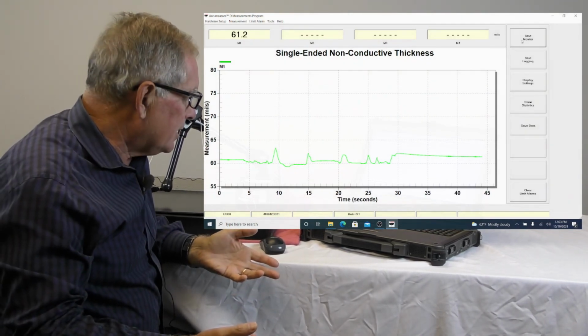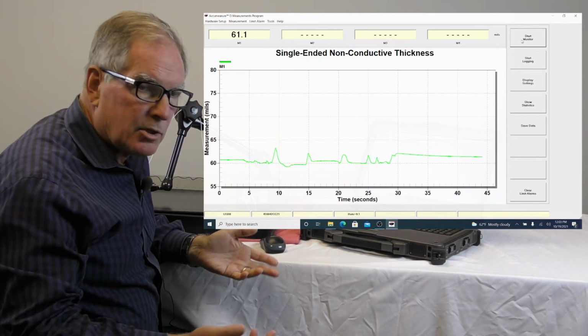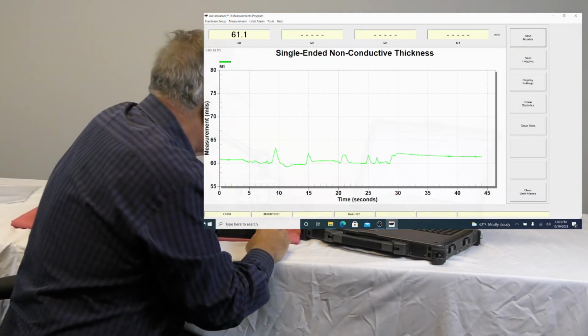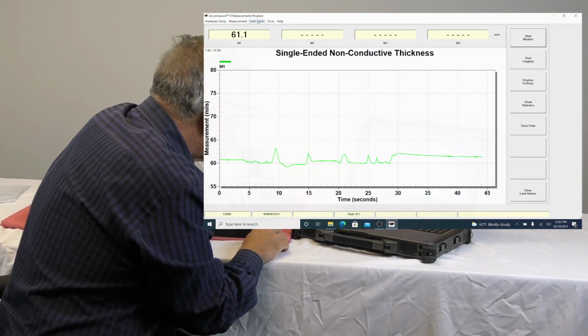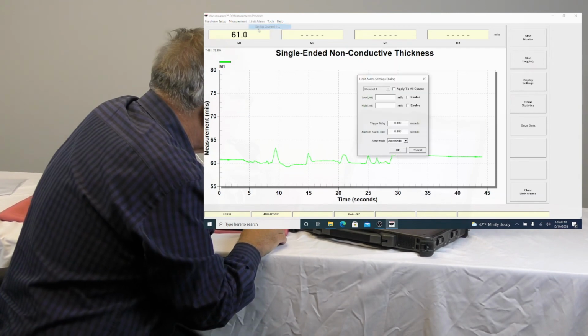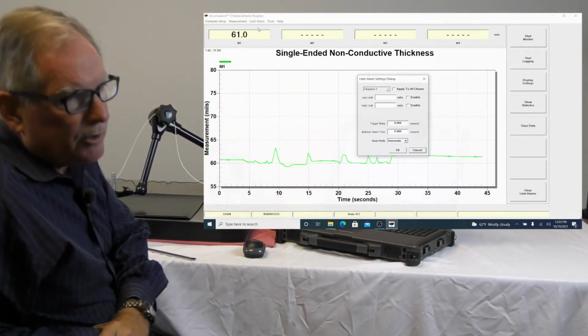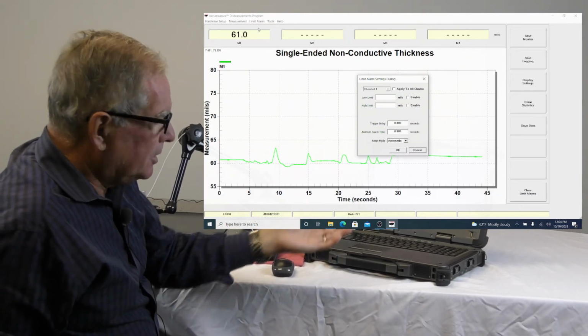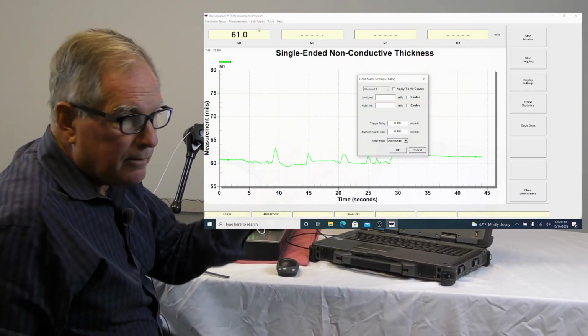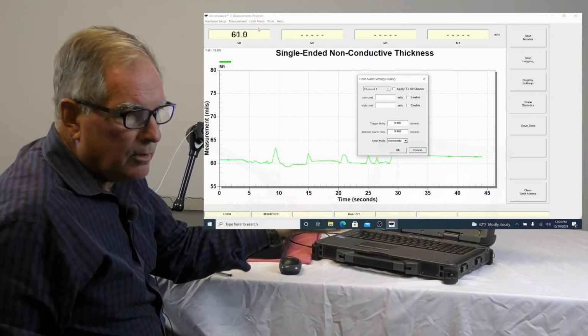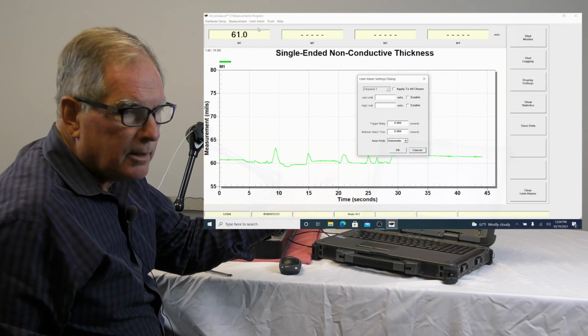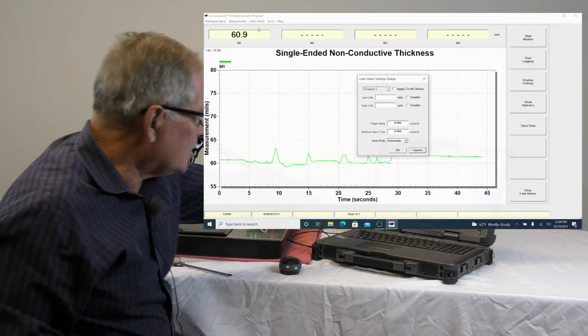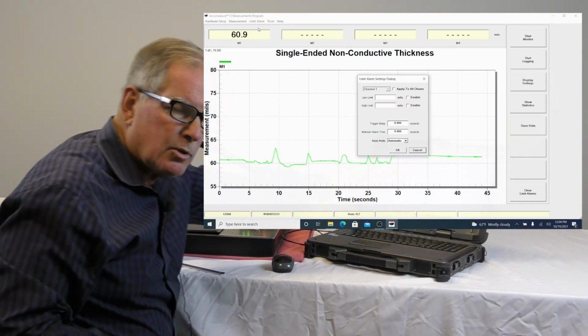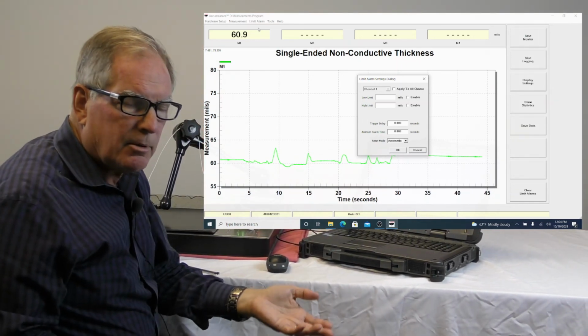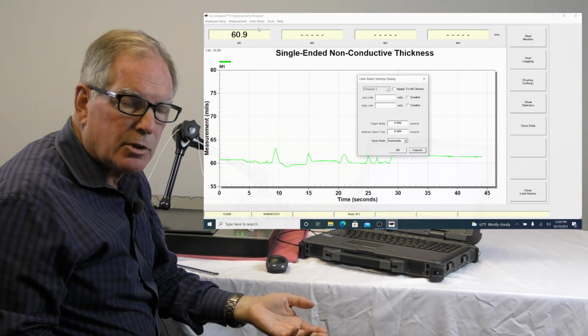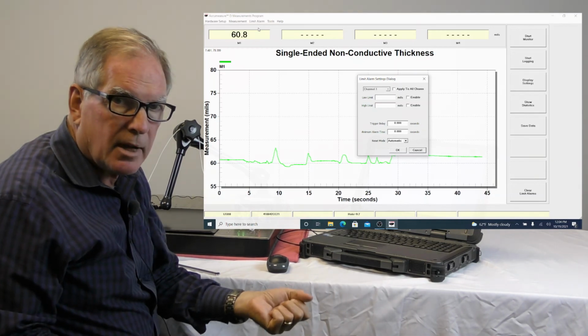So we can keep track of our in-process thickness measurements. And the other thing we can do too, and I'm just going to show you the screen here, is we have limit alarms. I can actually go in and set up an over limit alarm, which will allow the computer to talk to another board that has a relay on it, so you can have an alarm indication. Let's say for anything over 65 thousandths of an inch, you want a red light to turn on or an alarm bell to ring. We would set those alarm functions up in this display right here. So you can be data logging and also have audible or lamp indication that your process is getting out of the limits that you have set for it.